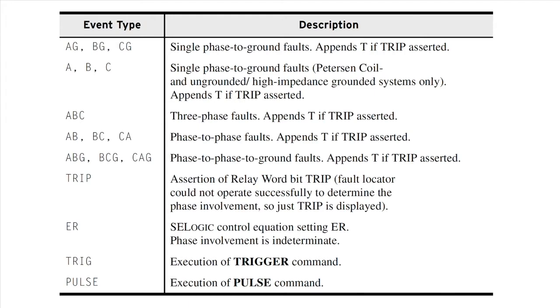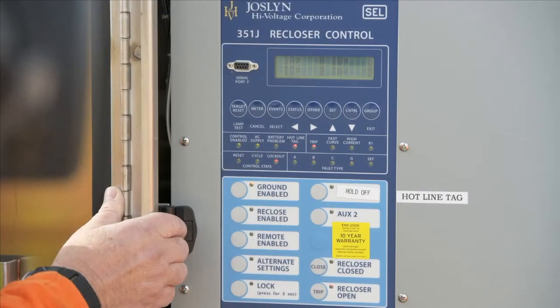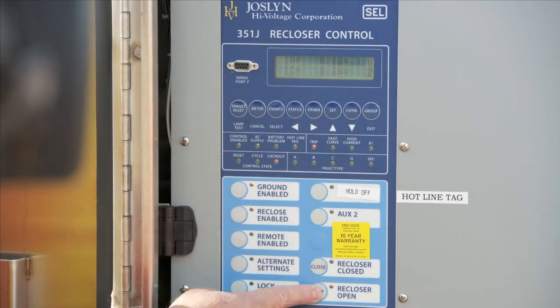The fault locator does not operate for ground faults on ungrounded, high-impedance grounded, or Peterson coil grounded systems. Also, the fault locator will not operate properly unless three-phase voltages are connected. The fault locator is most accurate when the fault currents last longer than 2 cycles. The relay reports the fault location if the EFLOC setting equals Y, and the fault locator operates successfully after an event report is generated. If the fault locator does not operate successfully, then $ signs are listed in the field.